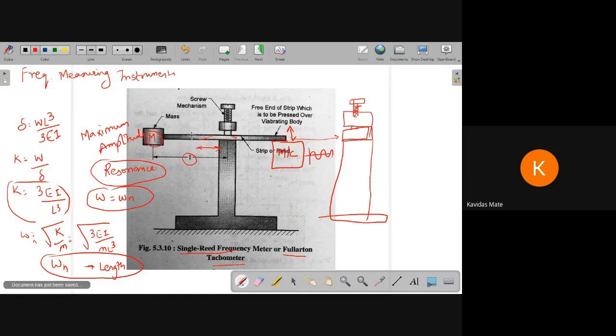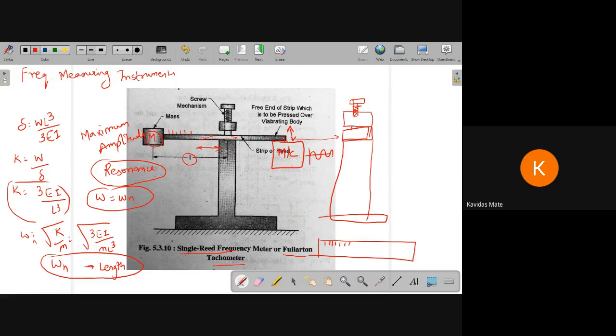How do we read it? On the top of this particular strip there is a calibration done. Whatever frequency is there, you can directly judge it — for this particular length, directly this frequency; for another length, another frequency. You don't have to do all the calculations; it is directly given on the strip. What you need to do is attach it to the machine, get the maximum amplitude by adjusting the screw and moving the strip. That maximum amplitude corresponds to the frequency of the machine component you are measuring.